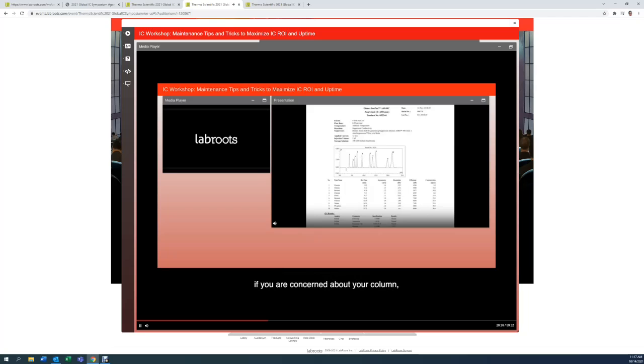If you are concerned about your column, my recommendation would be to go and recreate your test chromatogram. If you can recreate the test chromatogram, you will really confirm that the column itself is in good working order. So your test chromatogram is very important. Make sure they are kept. The other thing about the test chromatogram is it gives you the back pressure of that particular column at the time of manufacture. We can see on this column it came in around the 1500 psi mark or thereabouts.